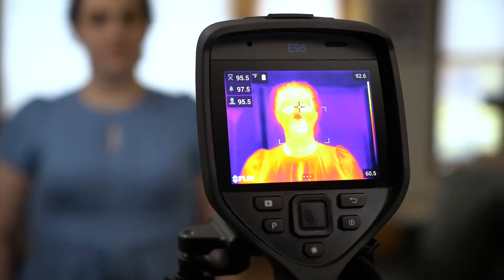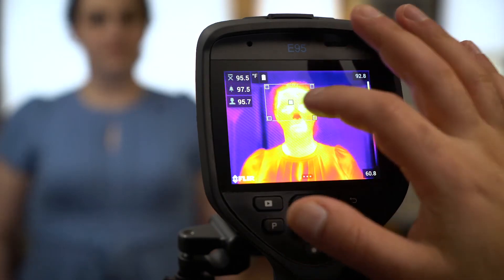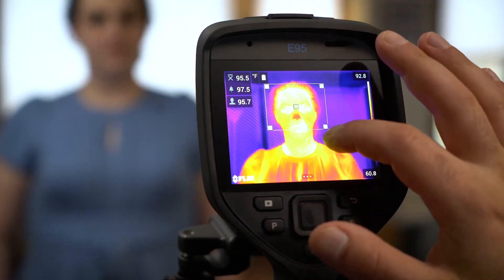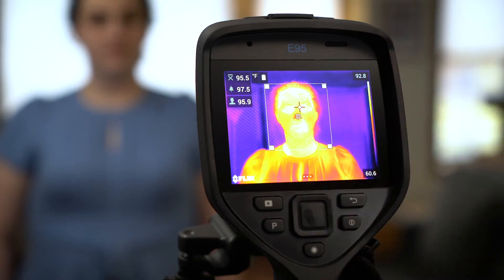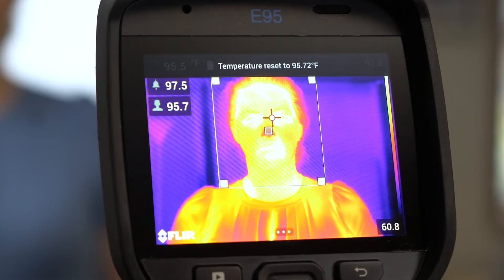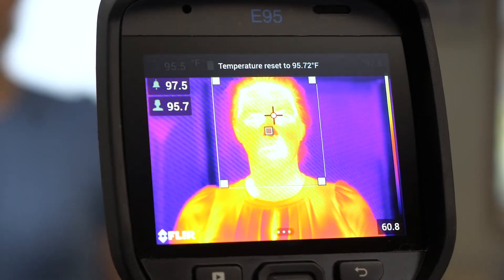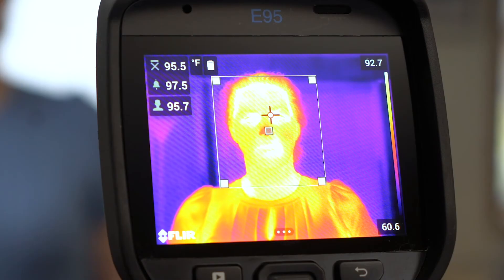We'll set our baseline using a person whose body temperature is within normal range, placing the area of interest over our subject. Press the P button to set the baseline. The camera has now been set to alert us when it detects a temperature over 2 degrees higher than the baseline.